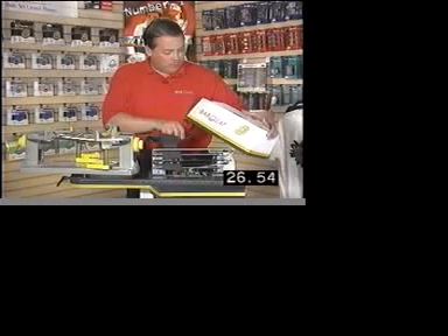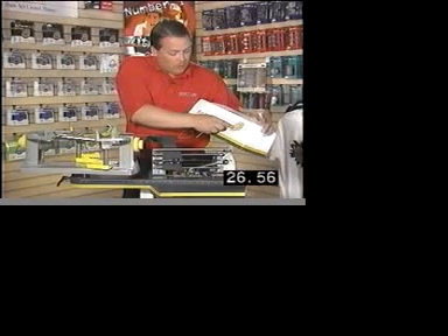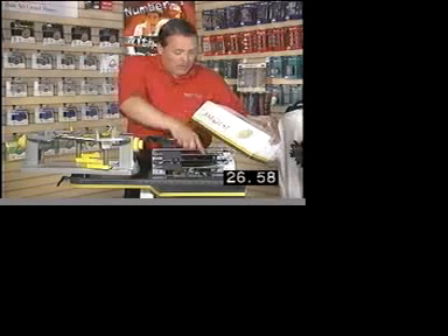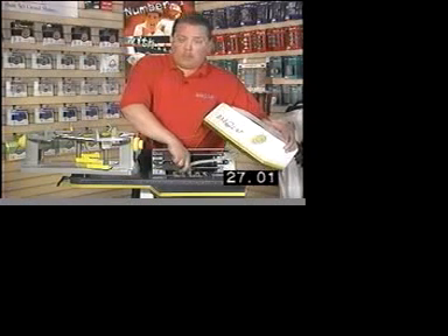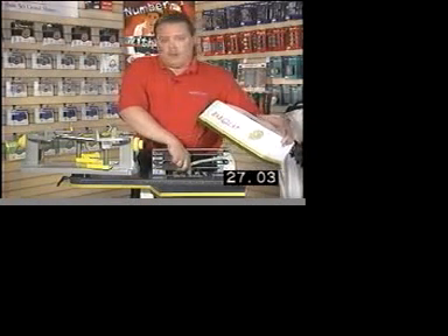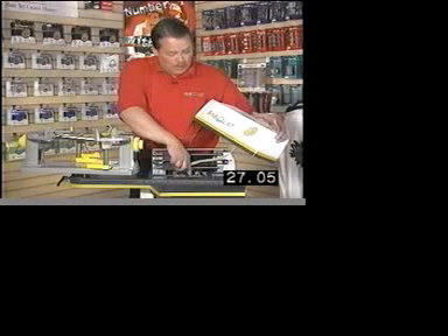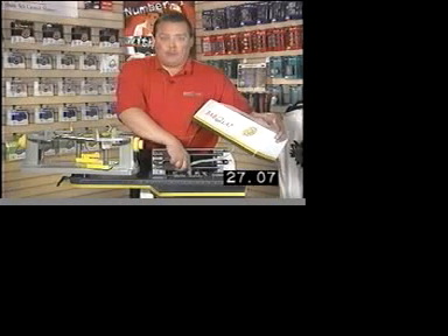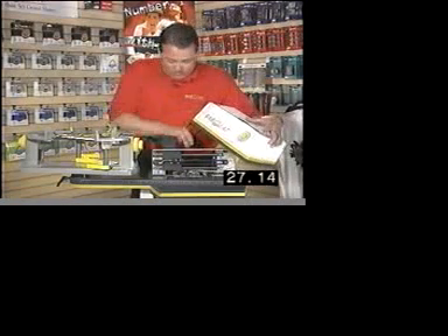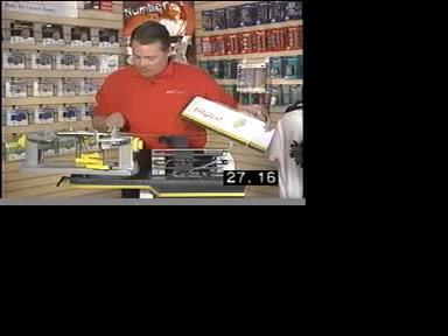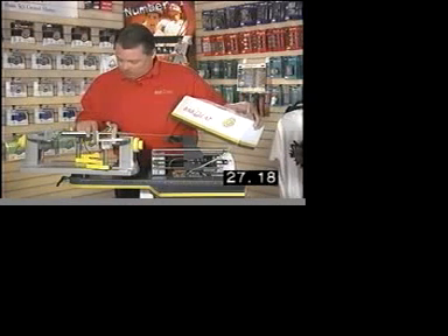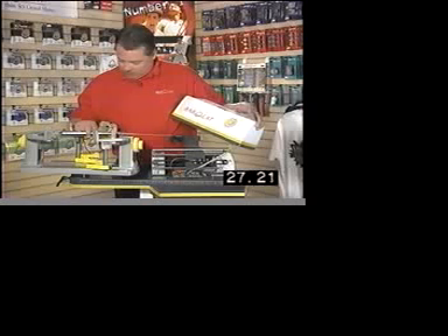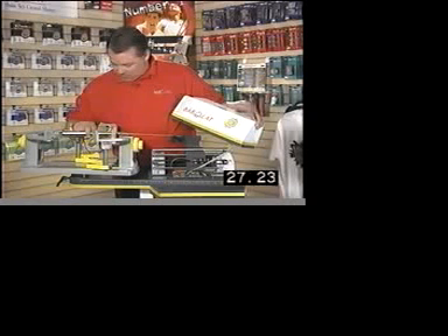The next thing you want to do is release tension and set your machine up to 30 kilos. Now I know it says 35 on the calibration pod here, but we don't want to go that tight. Up to 80 pounds on a calibrator is not something that you want to do. I suggest staying at 30 kilos or 65 pounds. So we set it to 30 kilos and we'll pull tension. And we're about a half a kilo off here.